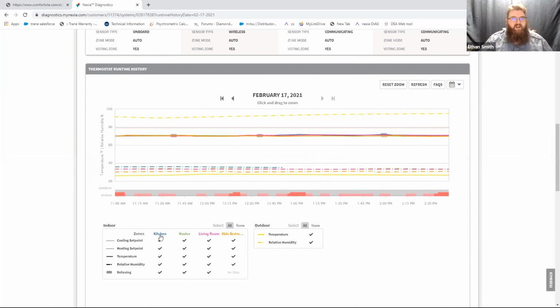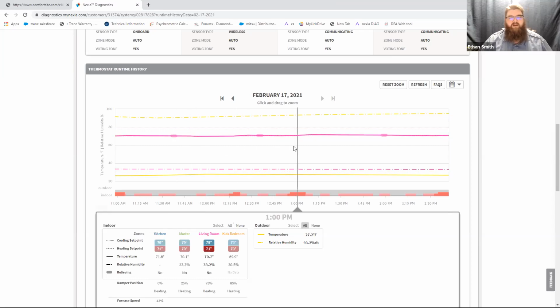So now the diagram can be a little muddy, so you can come in here and turn off any set of data points. If I didn't care about any of the cooling data points, I could click these check marks for the cooling, and it will make my cooling set points go away. And I'm hosting a Zoom session, so this is going to take its dear sweet time, but we can see those cooling set points going away here. If I only want to look at one zone, I can click off all my zones except, say, the living room, and it'll make all my data theoretically go away except for the living room. Taking its dear sweet time. There we go. So there I have just my living room.